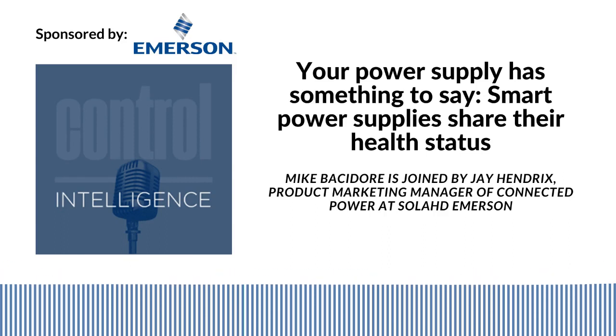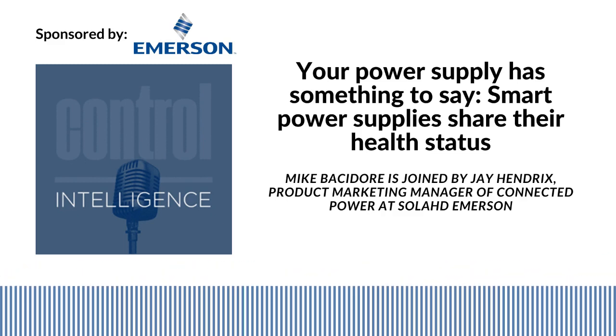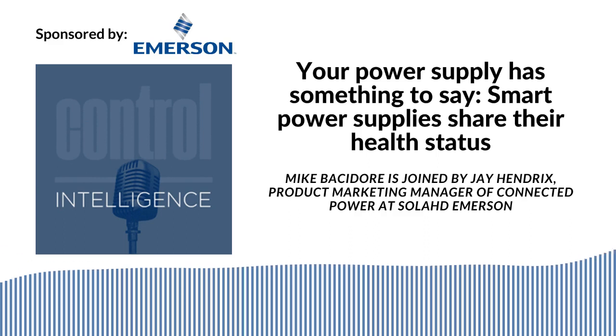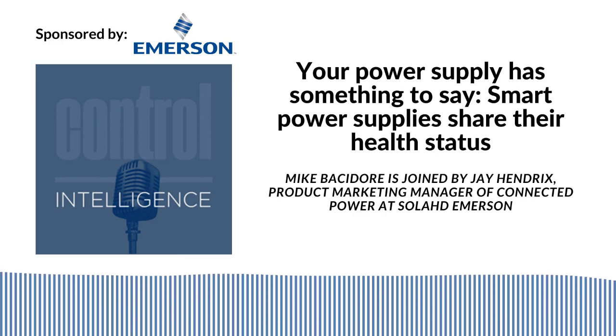But from an Ethernet standpoint, there's high speed. There are some good options here: Ethernet/IP, EtherCAT, Profinet, and even Modbus over TCP would be great options to provide communication from your power supply onto a network. In the process world, another heavily used protocol is HART, Highway Addressable Remote Transducer Protocol, and that's used in process control situations, and that may be a great option because you could leverage something that you're already using. And some suppliers have even adopted IO-Link, which is a short distance point-to-point protocol. So that may be an option for your situation.